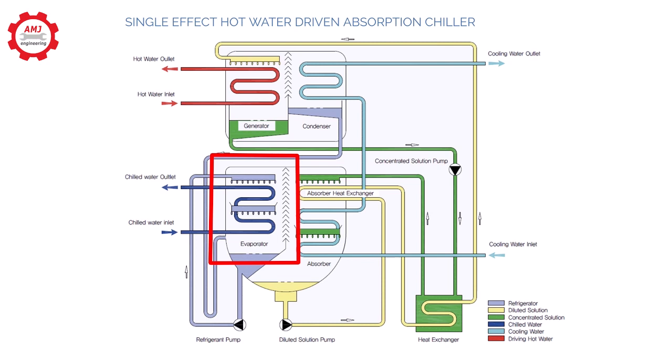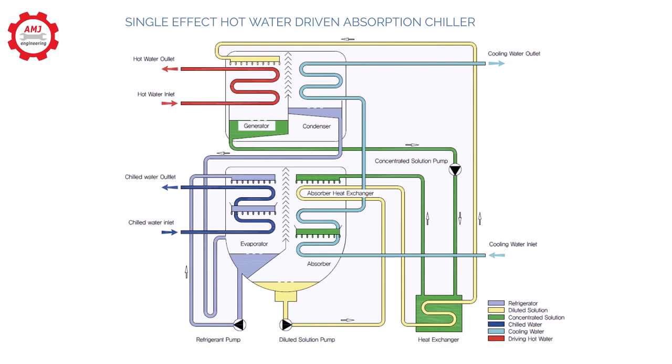Evaporator: Liquid refrigerant is dropped in pressure when it flows through an orifice into the evaporator. Due to the lower pressure in the evaporator, flashing takes place. The flashing cools the remaining liquid refrigerant down to the saturation temperature of the refrigerant at the pressure present within the evaporator.